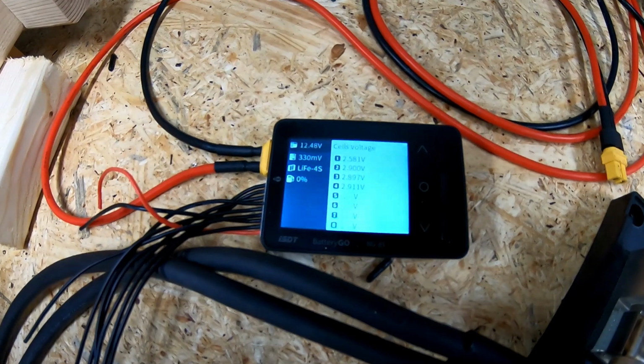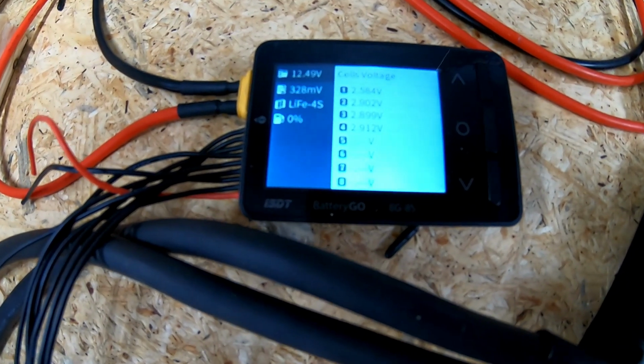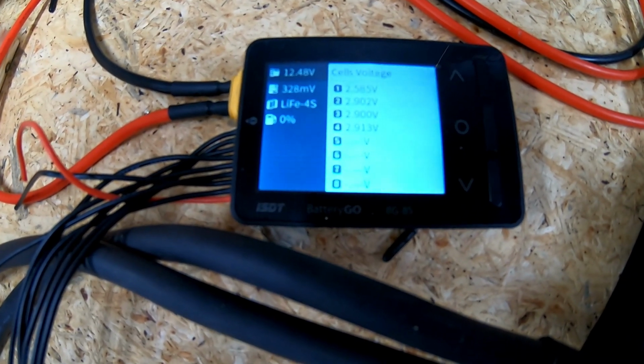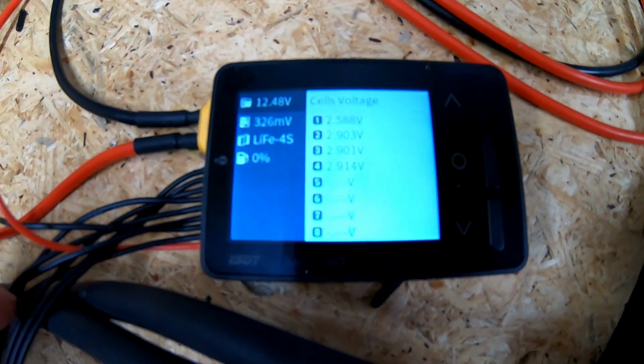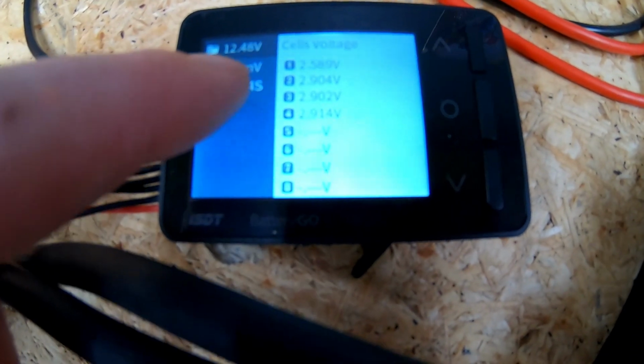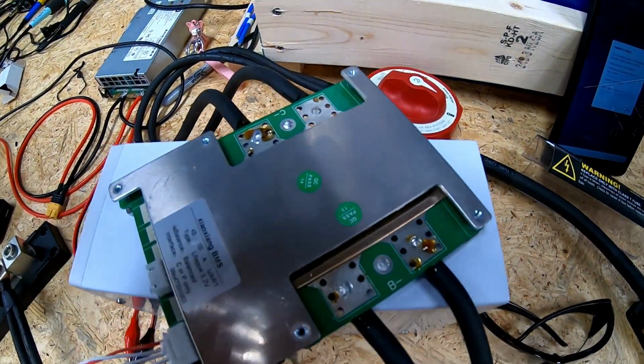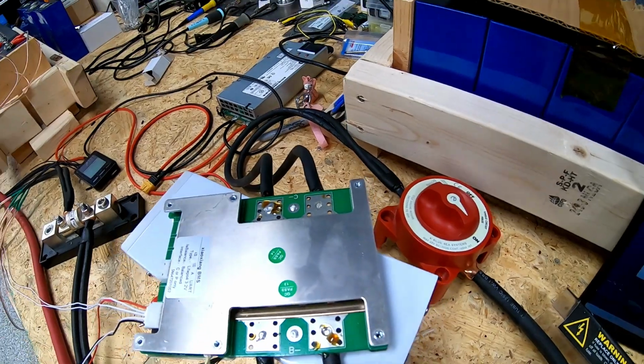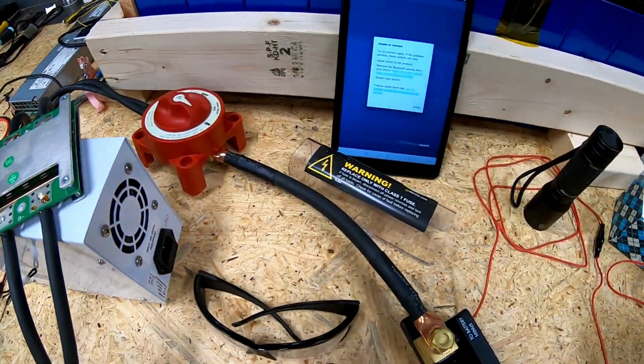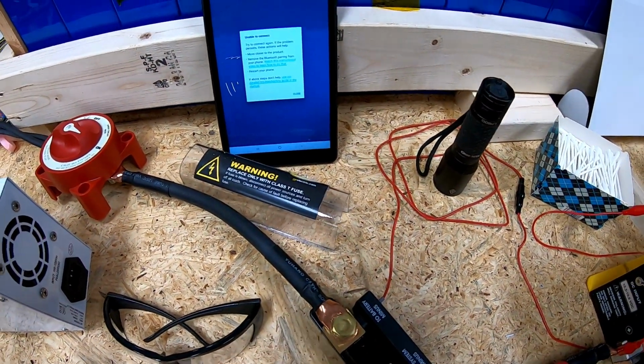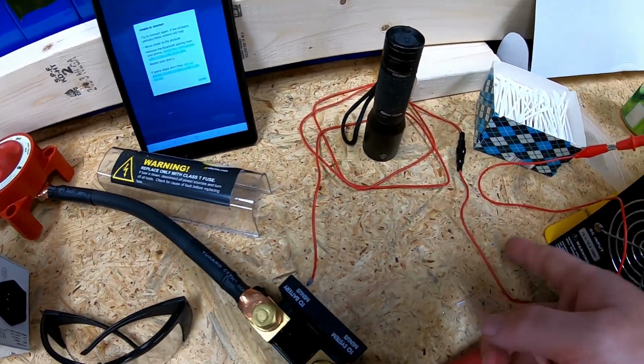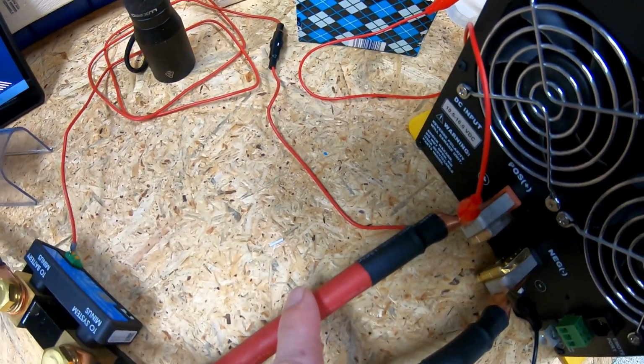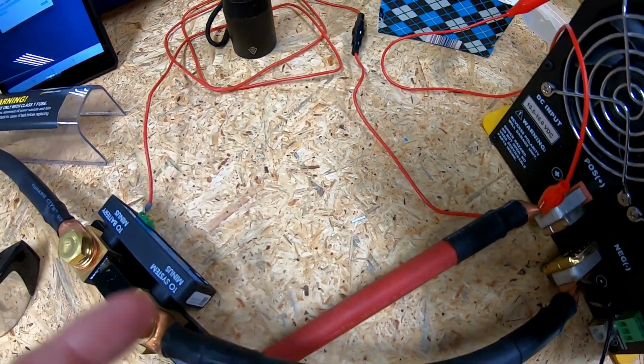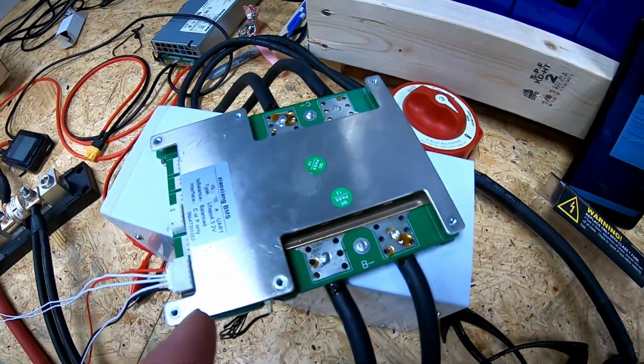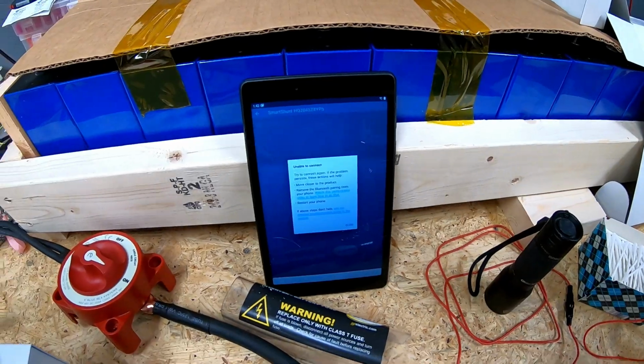Yep, 2.5 volts. Looks like our number one cell dropped out. So we dropped out at 2.5 volts on our number one cell, which means our BMS stopped outputting power, which is why we lost communication to our SmartShunt, because our SmartShunt is tied into the positive side of the battery directly, but then it needs to get its power through the BMS, so that's why we lost our connectivity there.